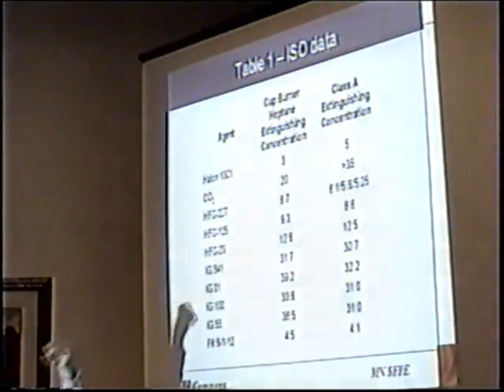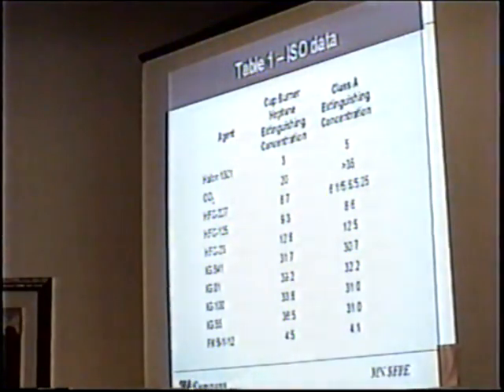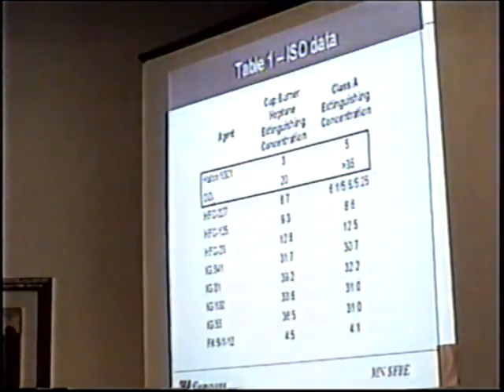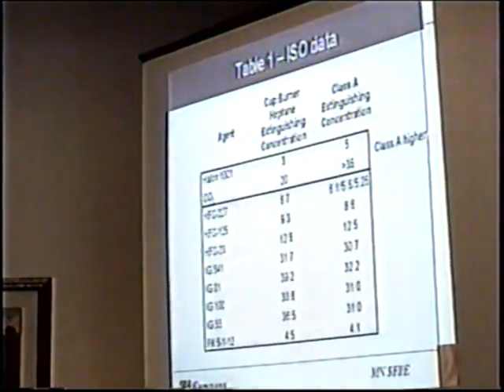Well, besides that, 227 has 3 tests. That's actually data. The 6.1 is the ISO data. Then the 5.8 to 5.25, those are both NFPA 2001 that are UL data. The thing about this here is that for Halon 1301 and CO2, the Class A value is higher. For all the clean agents, the Class A is lower.